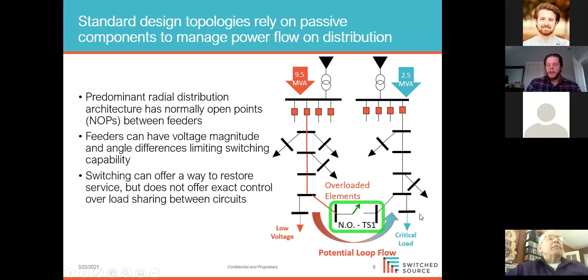So we started pitching the concept of putting a tie controller at these distribution circuit ties, giving utilities dynamic control over where capacity was on their system. If the device fails, the system fails normal, so to speak, and you'd just go back to having a normally open tie between these distribution circuits. We thought we'd knocked it out of the park finding this initial use case, but it's been under development for 2 or 3 years now.